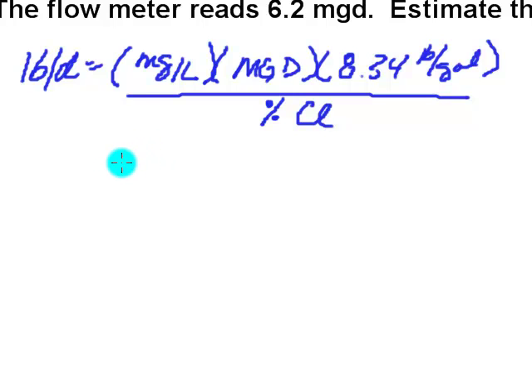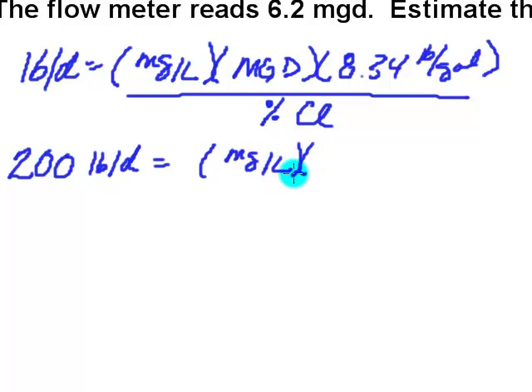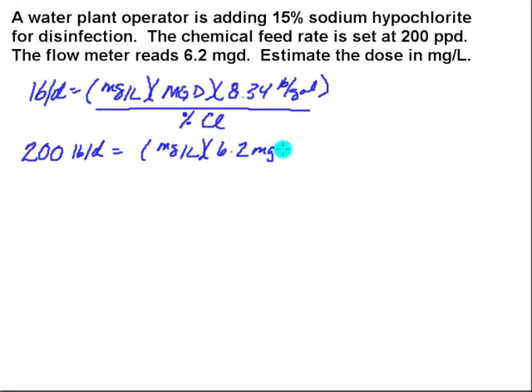So let's start plugging in what we know. They gave me the actual feed rate, we know that this is 200 pounds per day. Milligrams per liter is unknown. The flow rate is 6.2 mgd. We're going to multiply that by our conversion, 8.34 pounds per gallon.